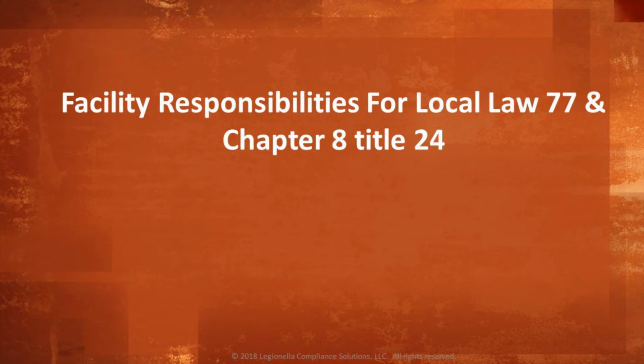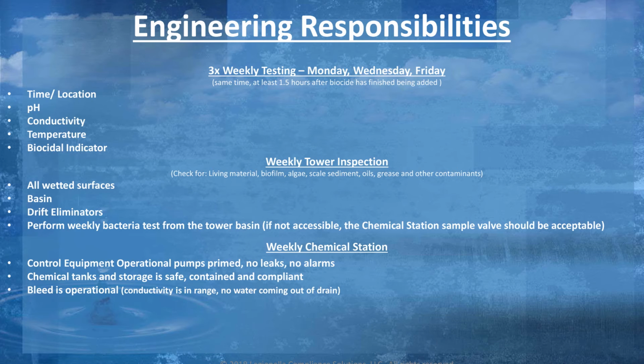Facilities with cooling towers must stay in compliance with NYC Local Law 77. This presentation will go over the major responsibilities a facility manager or responsible person must do in order to stay in compliance. To begin, we will cover all of the items that need to be done on a weekly basis by the responsible person. First, the responsible person must test the cooling tower system 3 times a week.